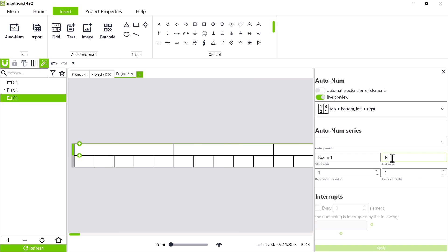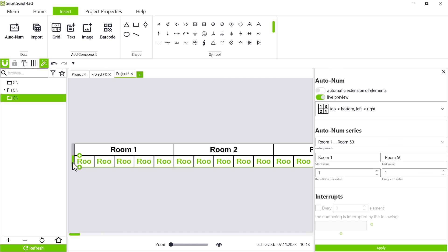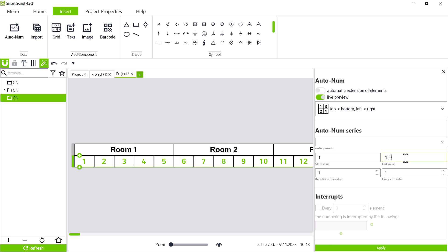Now we open the window autonum and mark the top section, can check the box for live preview and create sections from room 1 to room 50. We then want to number individual terminal blocks through. At the fourth and fifth place, however, the numbering should be interrupted by a n and a pe terminal block. So we enter a start value of 1 and an end value of 150 and check the box for interrupts. Now we enter the number of elements to be numbered before the interruption. In our case, three elements and in the box below, we specify what should be written in the interruption, in this case n.